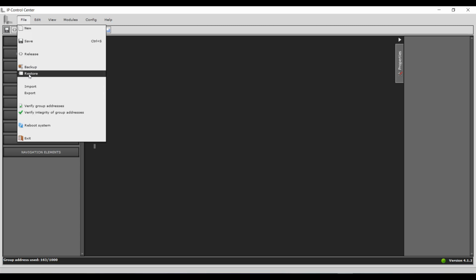With Import and the selection ESF Read, the ESF file of the ETS project is loaded, as already explained. This contains the group addresses created in the ETS project with their full name. If special characters, such as Greek or Chinese, have been used, the corresponding character set can be pre-selected. In addition, it is possible to define whether existing character texts or defined subdata types should be overwritten.